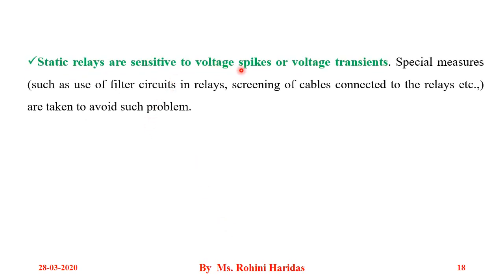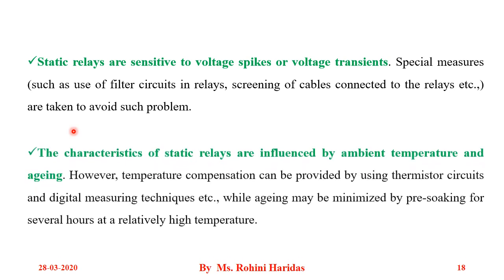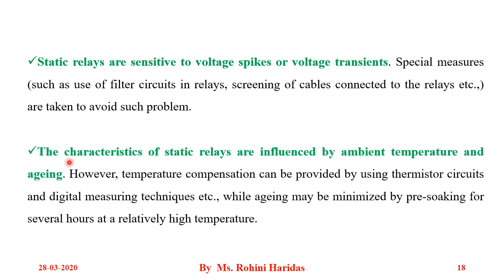Static relays are sensitive to voltage spikes or voltage transients. Special measures such as the use of filter circuits in relays and screening of cables connected to the relays are taken to avoid such problems. The characteristics of static relays are influenced by ambient temperature and aging. Temperature compensation can be provided by using thermistor circuits and digital measuring techniques, while aging may be minimized by pre-working for several hours at rated conditions.